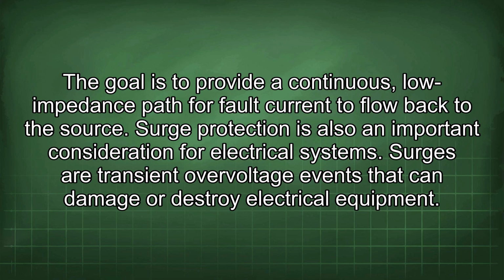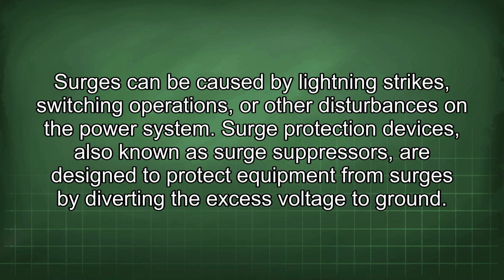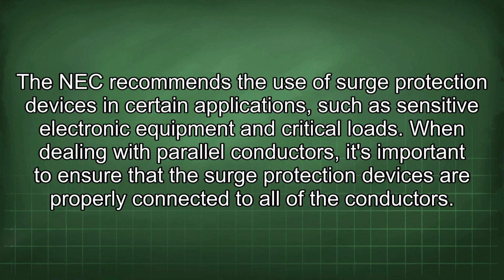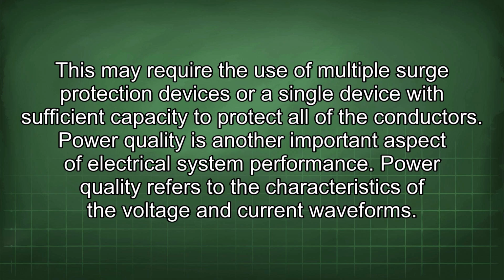Surge protection is also an important consideration for electrical systems. Surges are transient overvoltage events that can damage or destroy electrical equipment. Surges can be caused by lightning strikes, switching operations, or other disturbances on the power system. Surge protection devices, also known as surge suppressors, are designed to protect equipment from surges by diverting the excess voltage to ground. The NEC recommends the use of surge protection devices in certain applications such as sensitive electronic equipment and critical loads. When dealing with parallel conductors, it's important to ensure that the surge protection devices are properly connected to all of the conductors. This may require the use of multiple surge protection devices or a single device with sufficient capacity to protect all of the conductors.